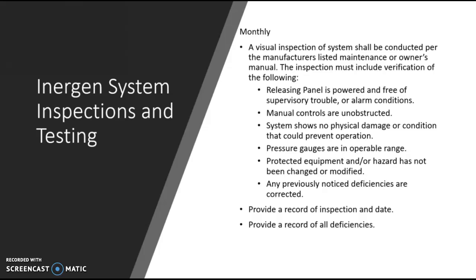And the visual inspection of the system needs to be conducted per the maintenance of the owner's manual, naturally. But the releasing panel is powered and free of supervisory trouble, alarms, and conditions. We want to make sure that all troubles and supervisory issues are taken care of on all of our panels. Manual controls are unobstructed. System shows no physical damage or condition. Even if it's a dent or something like that, we want to make sure it's completely safe and protected.